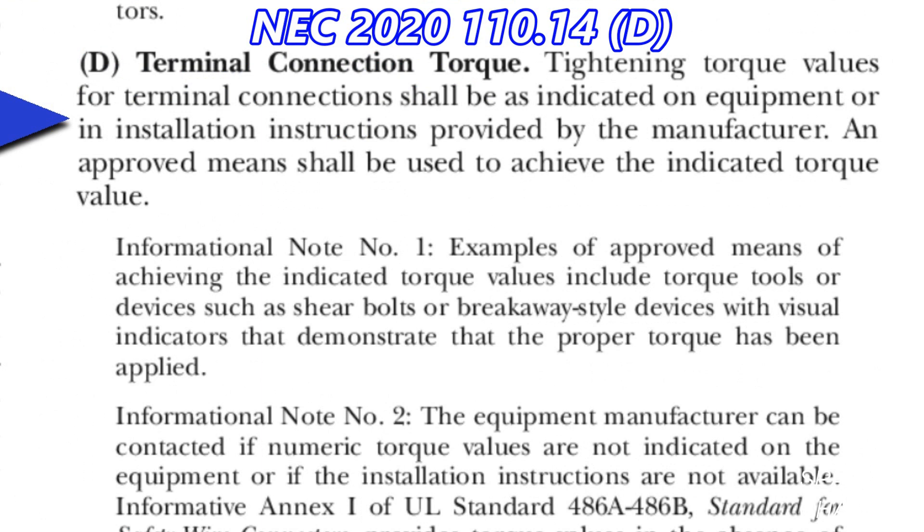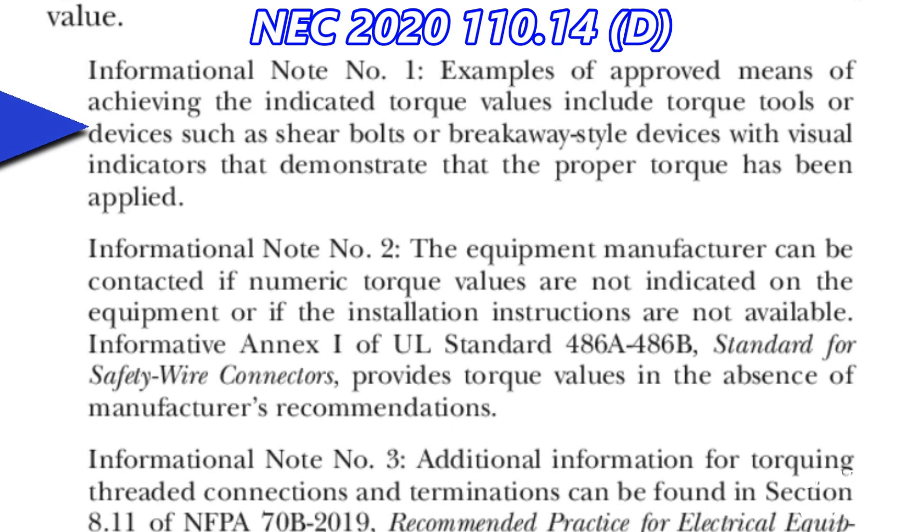Tightening torque values for terminal connection shall be as indicated on equipment or in installation instructions provided by the manufacturer. An approved means shall be used to achieve the indicated torque value.